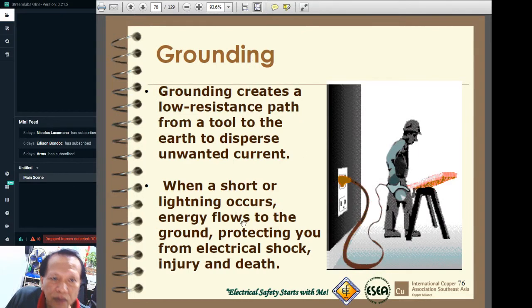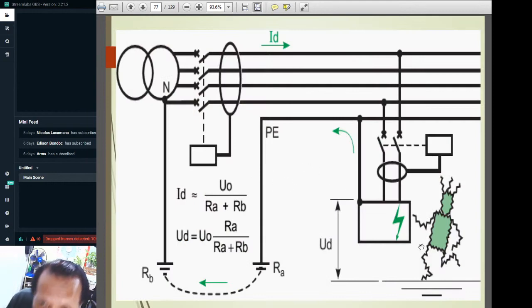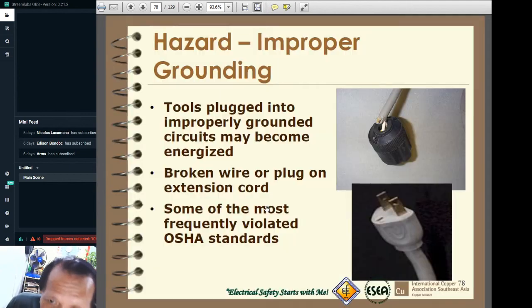Grounding creates a low resistance path from a tool through the earth. So again, usually our plug is provided with a ground lug. So our home run, circuit home run, should have a grounding connection. So that will protect the personnel working with a portable tool like this one. So sometimes we cut it, no. So that's not a good practice. No? Okay, so here is a schematic that when this person touches an enclosure that is not adequately grounded, he gets electrocuted. Okay, so we should avoid cutting the grounding electrode like this one.